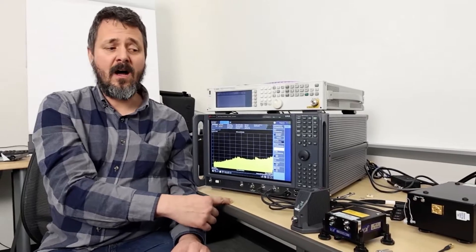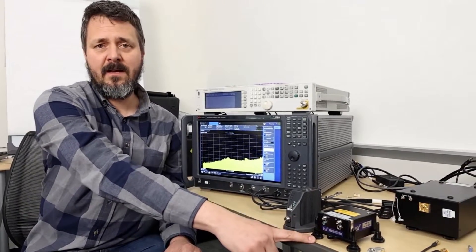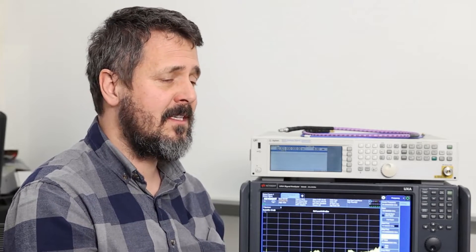We'll be doing this two different ways. One is with the frequency range extender on the UXA and then we will also be using the VDI downconverter. Noise figure measurements above 50 gigahertz are becoming more common and more necessary as customers inevitably make measurements higher in frequency with wider bandwidth. You'll often need to make noise figure measurements on amplifiers and frequency converting devices.